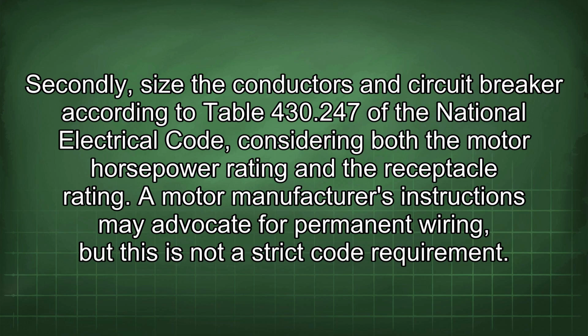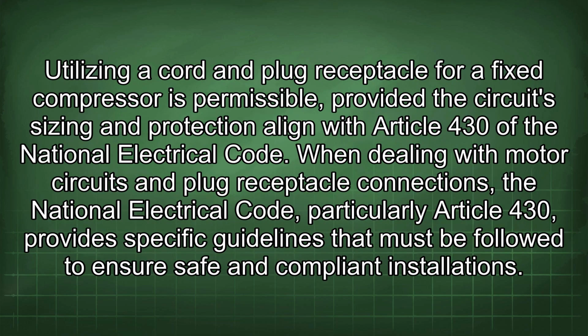A motor manufacturer's instructions may advocate for permanent wiring, but this is not a strict code requirement. Utilizing a cord and plug receptacle for a fixed compressor is permissible, provided the circuit sizing and protection align with Article 430 of the National Electrical Code. When dealing with motor circuits and plug receptacle connections, the National Electrical Code, particularly Article 430, provides specific guidelines that must be followed to ensure safe and compliant installations.